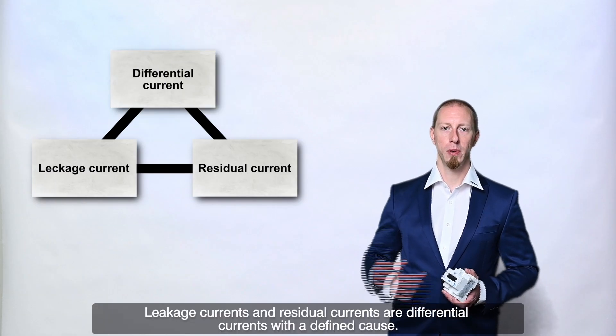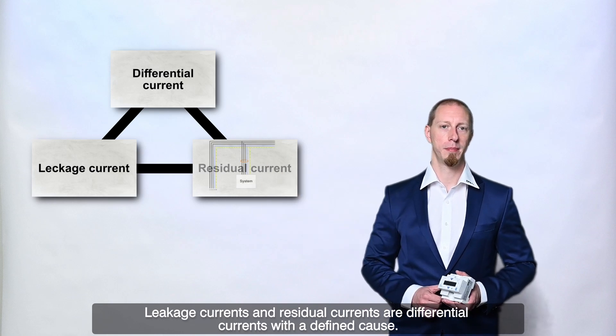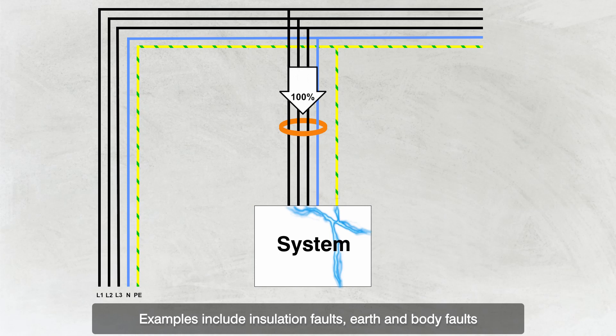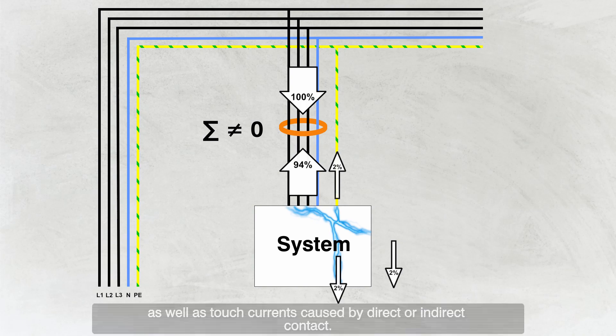Leakage currents and residual currents are differential currents with a defined cause. Residual currents, as the name implies, are due to faults in the system. Examples include insulation faults, earth and body faults, as well as touch currents caused by direct or indirect contact.